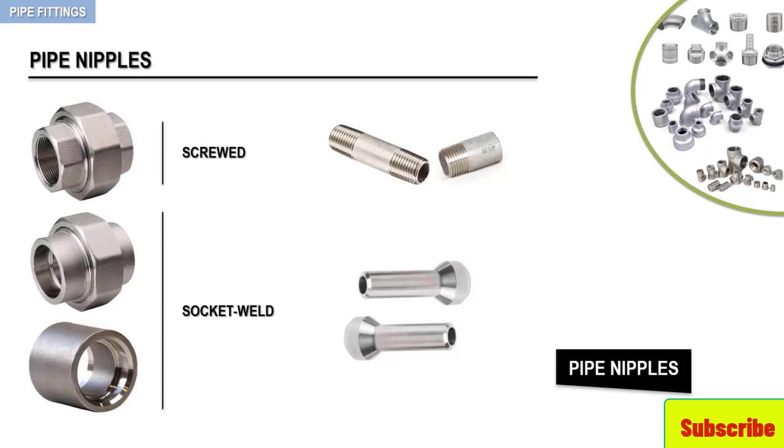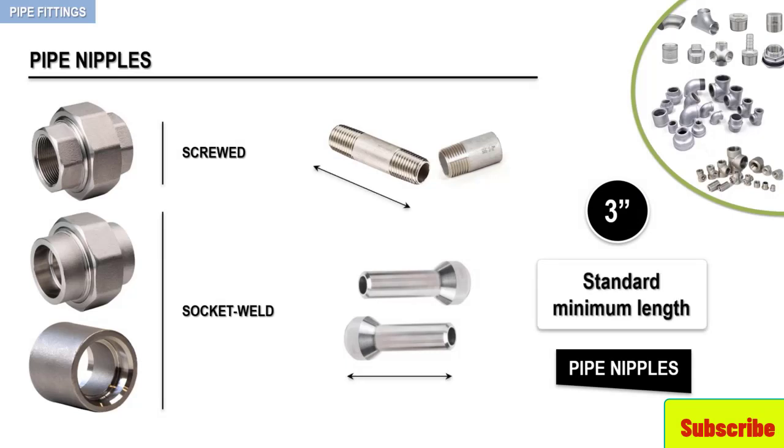Pipe nipples can vary in length depending upon the distance required to fabricate the pipe configuration. A close nipple is one that allows for the minimum assembly length between two pipe fittings. Screwed and socket-weld configurations have a certain amount of pipe length loss due to thread engagement and socket depth. Because thread engagement and socket depth varies depending on the pipe's nominal size, each pipe size has a different minimum length for the dimension of a close nipple. Many companies will use 3 inches as the standard minimum length of pipe nipples, as this length will accommodate the pipe length lost on both ends of the fitting, as well as provide sufficient wrench clearance during assembly for the larger screwed pipe sizes.